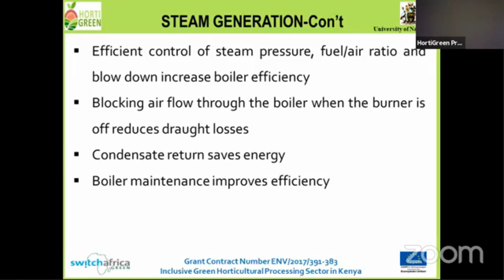So return of that steam condensate to the boiler, to become part of the boiler feed water, saves energy. And of course, proper boiler maintenance improves its efficiency. For example, when soot builds up on the heating surfaces, then the transfer of heat to the water, and therefore the utilization of that heat for steam generation, is reduced. I've already talked about insulation.